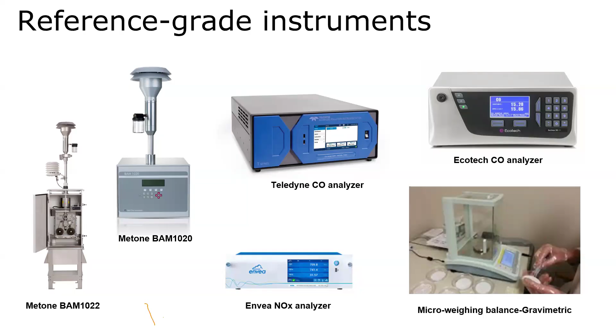Okay, these reference grade instruments: USEPA gives a label called FRM and FEM, Federal Reference Methods and Federal Equivalent Methods. Now, here I'm trying to say that all the instruments I have shown in the earlier slide are mostly rack mounted and sheltered, because in order to use them, all the instruments need to be rack mounted and these racks should be sheltered. It requires a conditioned atmosphere, like we need to maintain the temperature in the shelter, we need air conditioners. At the same time, they require conditioned power, meaning without leakage currents, and the earthing should be good. All those requirements are there for these instruments.